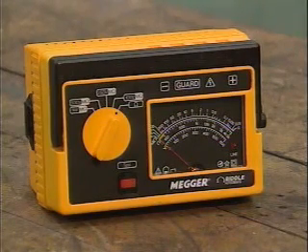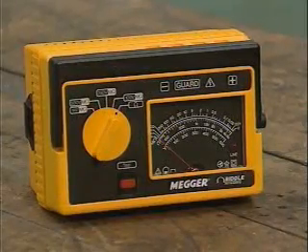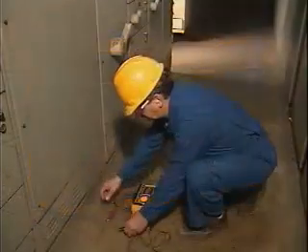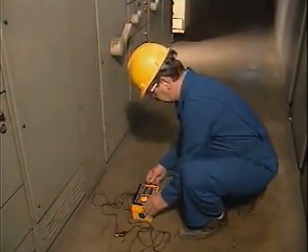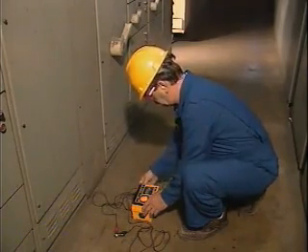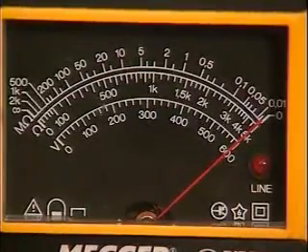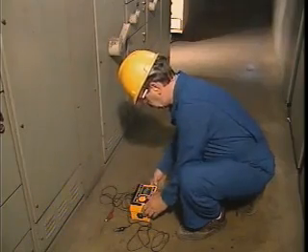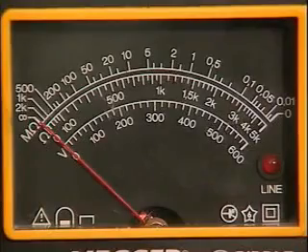There are several types of megohmmeters. Some are powered by a hand-cranked generator, and others are line-powered. The one used in our example is cranked by hand. Before using the megohmmeter to test for grounds, the electrician tests the instrument to make sure that it's operating properly. To do this, he clips the meter's two probes together and then operates the meter. The meter should indicate zero resistance, and it does. Next, the electrician separates the probes and operates the megohmmeter again. This time it indicates infinite resistance, as it should.